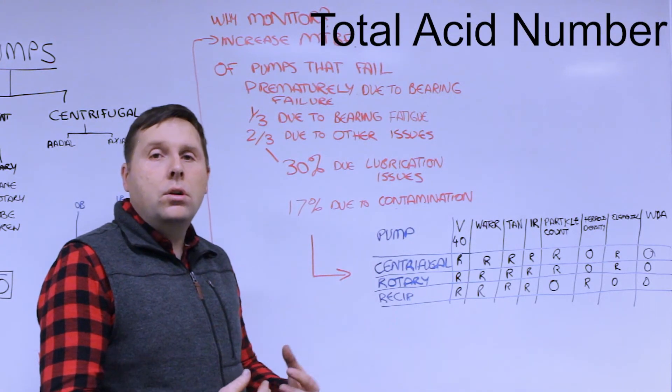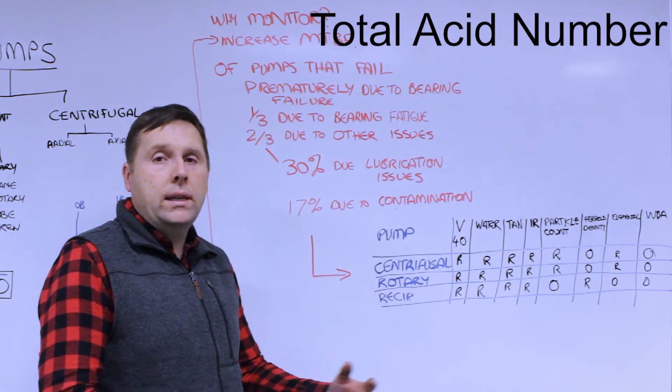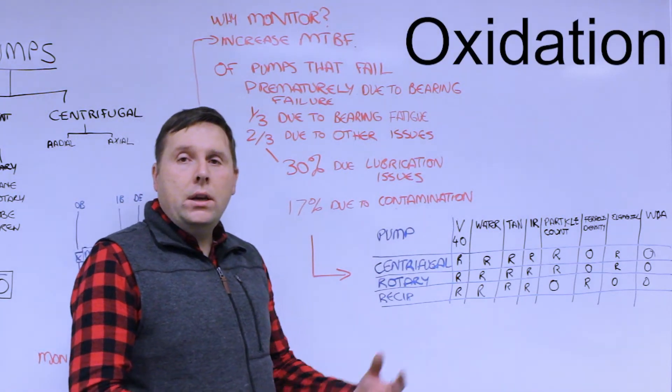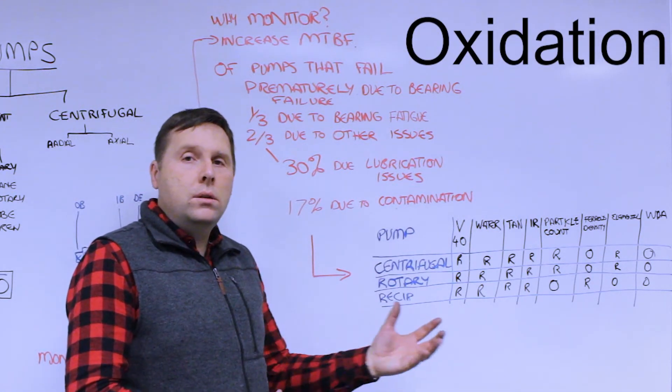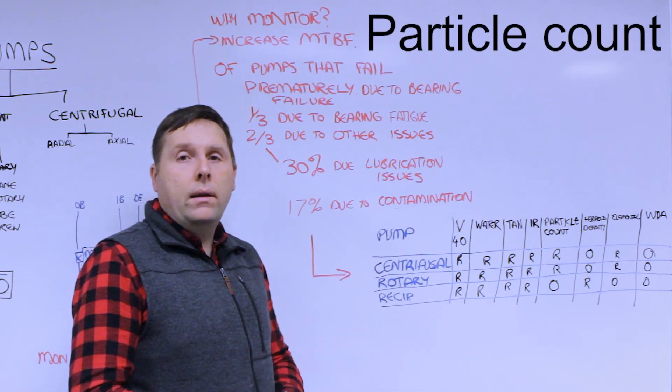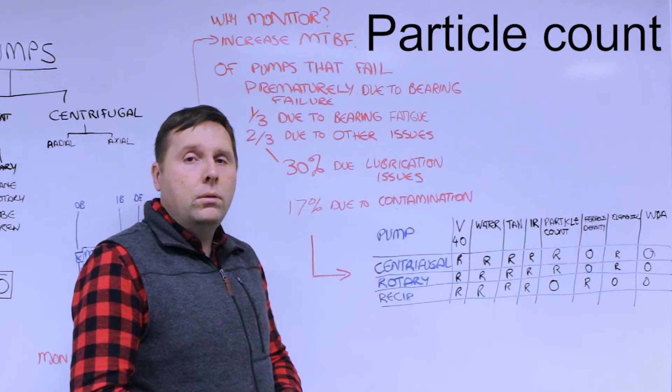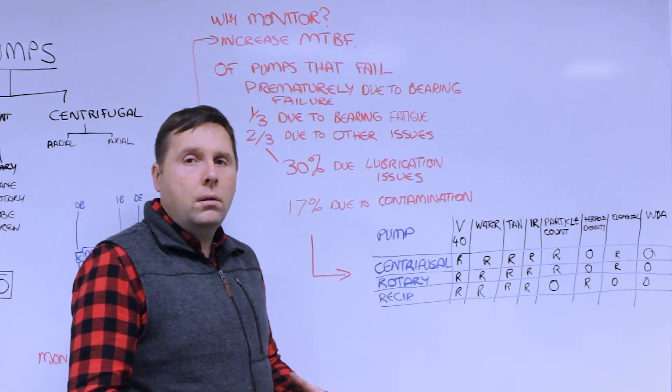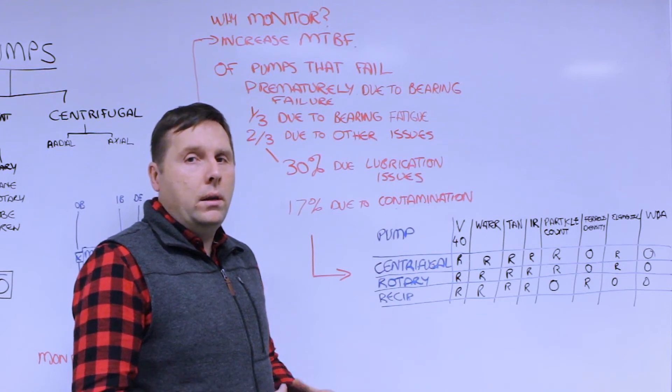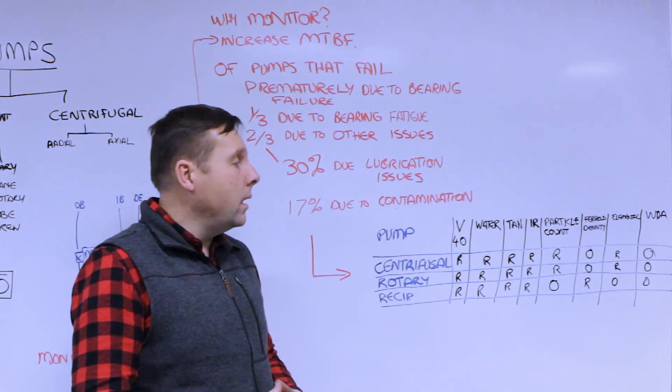Acid number to determine if the fluid is degraded or there's a lack of lubrication causing overheating. Infrared oxidation, a supporting guideline to determine if the oil is no longer fit for use. Particle count, a measure of the level of cleanliness of the fluid - particularly for bearings, it's critical. For other applications, you want to see if there's aggressive wear on the rotary or vane style systems.